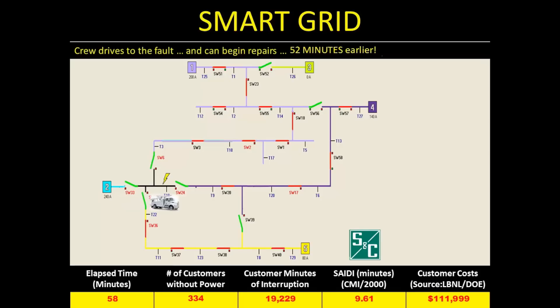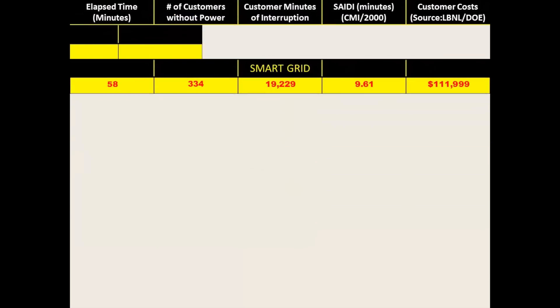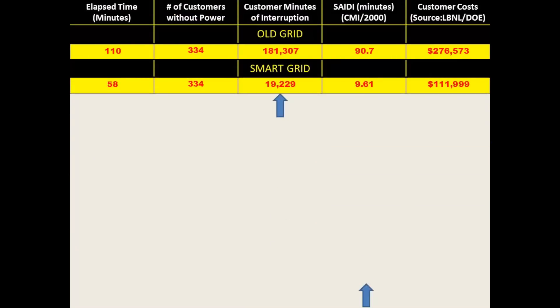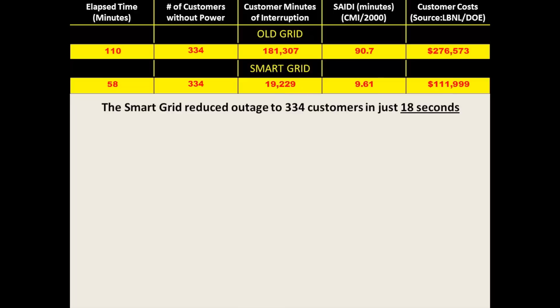All of the other numbers are a lot smaller than in the old grid case. Comparing the numbers, the cumulative customer minutes of interruption in the smart grid case are about 11% of what they were in the old grid scenario — and therefore so is the interruption duration index, SAIDI. The costs are also quite a bit lower. With the smart grid, we got down to 334 customers out of power in just 18 seconds, whereas the old grid took almost two hours to achieve that.